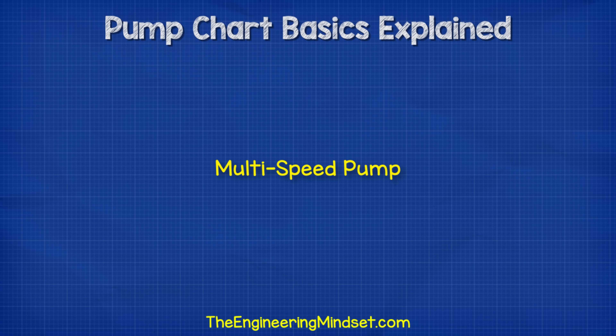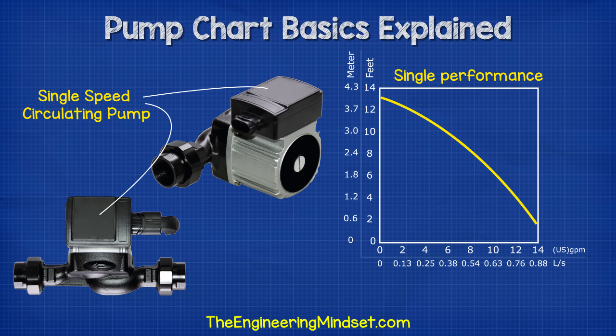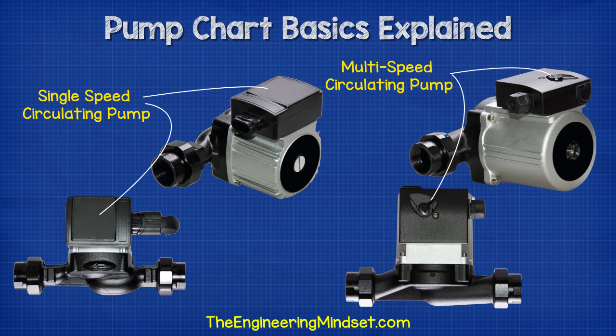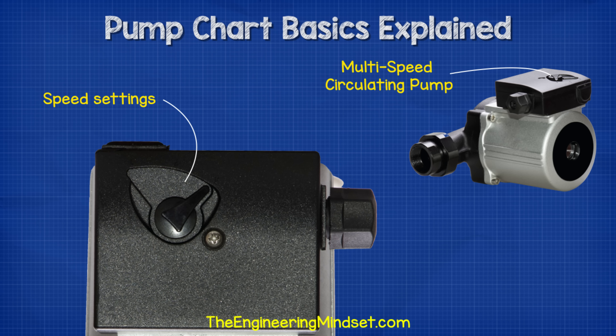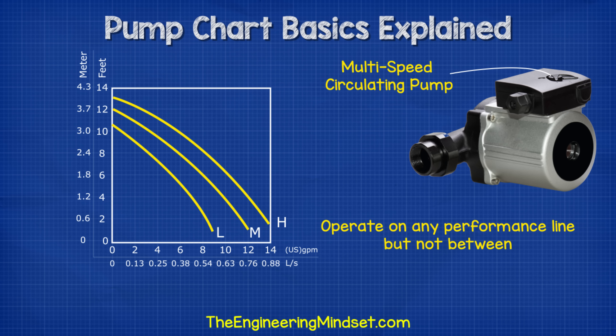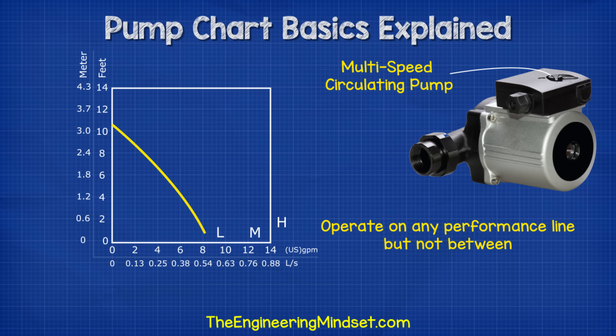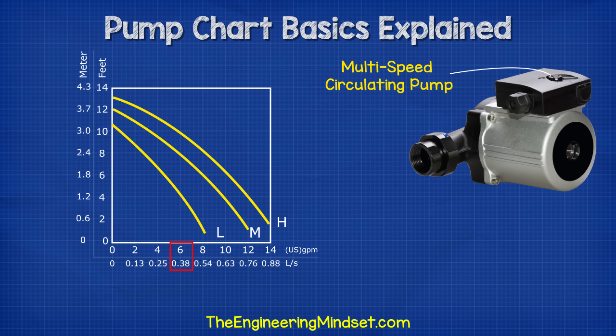Multi-speed pumps. Some pumps operate at a fixed speed and therefore have a fixed performance curve, but we can also get multi-speed versions which have the ability to switch between speed settings. Typically these come with three different speeds — low, medium and high — so these pumps will have a chart with three different profiles plotted on them. We can operate the pump at any of these curves, but not between them. So for this example, if we wanted 6 gallons per minute or 0.38 litres per second, then on setting one we would get around 4.2 feet of head, on setting two we would get 8 feet, and on setting three we would get around 9.8 feet.